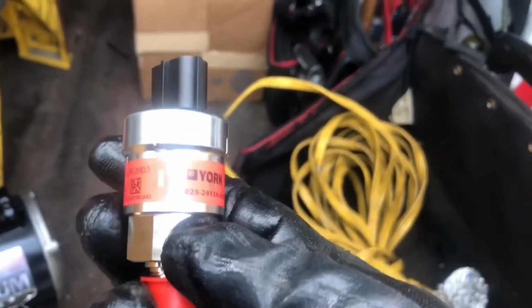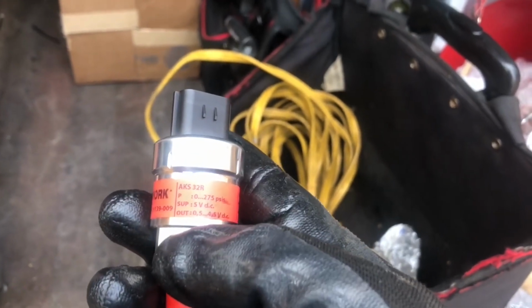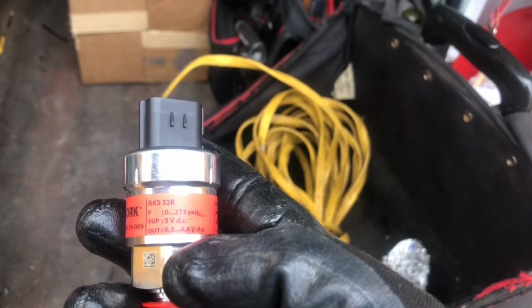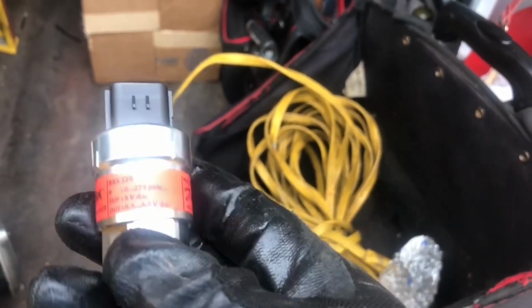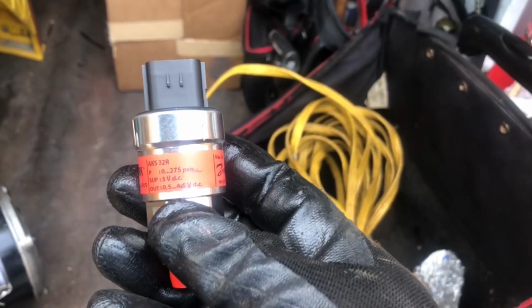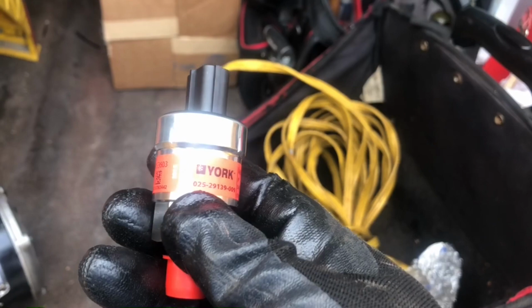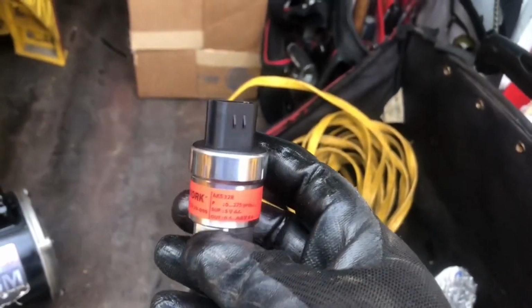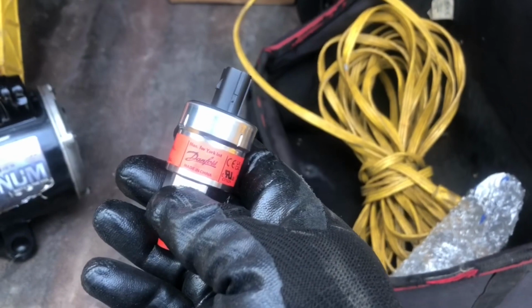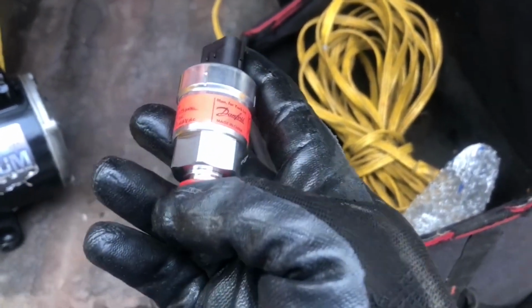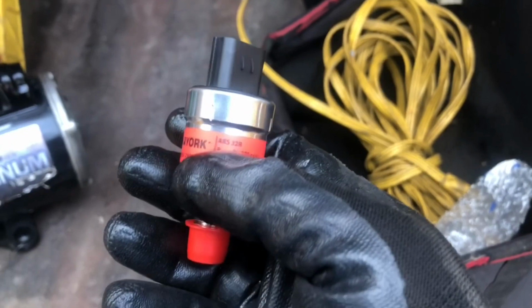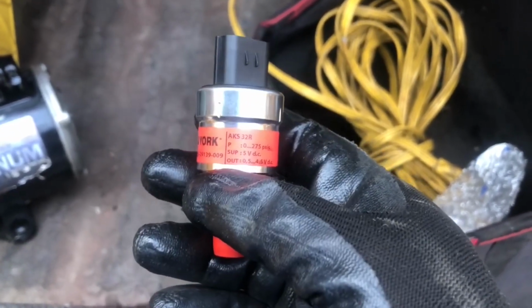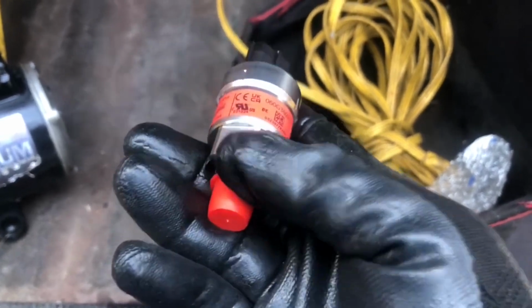Let me show you. And even for Yorks, they don't all use the same transducers too. Like even if it's a York, sometimes the DC voltage might differ as well. But it tells you all the specs. So it goes all the way to 275 psi. So just make sure that whenever you go ask for this part, you ask for the correct part, and you tell them specifically which part of the unit you're gonna be replacing. In this case, it's gonna be the oil pressure transducer that I'm gonna be replacing. So when I went, I gave him the model and serial number of my unit, and that's how they came up with this part right here.